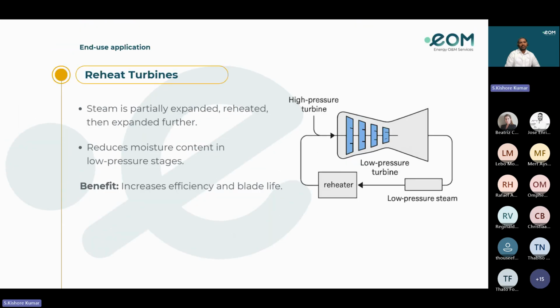Reheat turbines. Reheat turbines improve efficiency by reheating the steam between turbine stages, reducing moisture content and increasing the work output. So in the reheat turbine, steam is partially expanded, reheated, then expanded further. So it reduces moisture content in the low pressure stages, and the benefits are that it increases the efficiency and also the blade life.